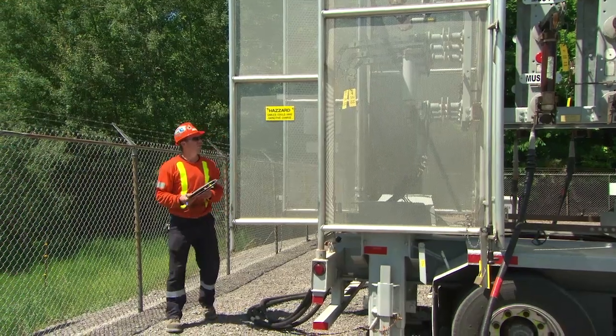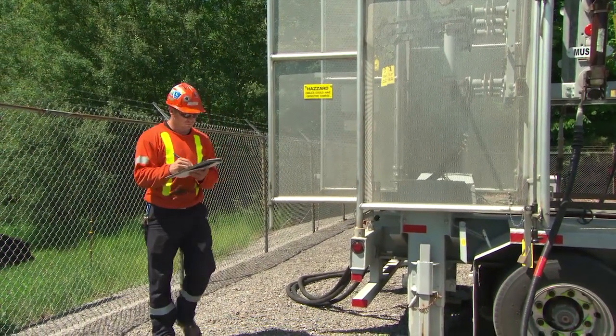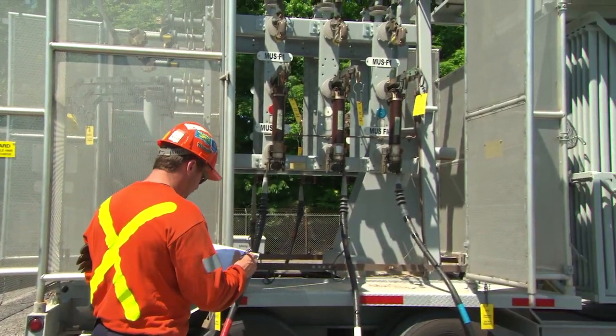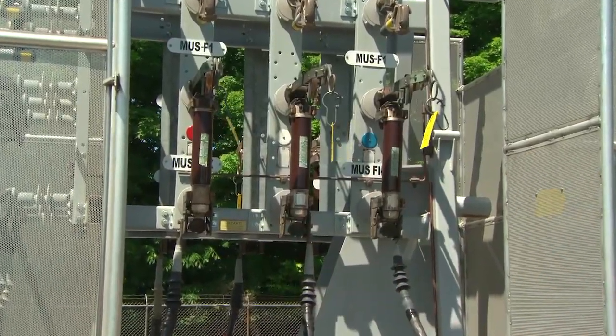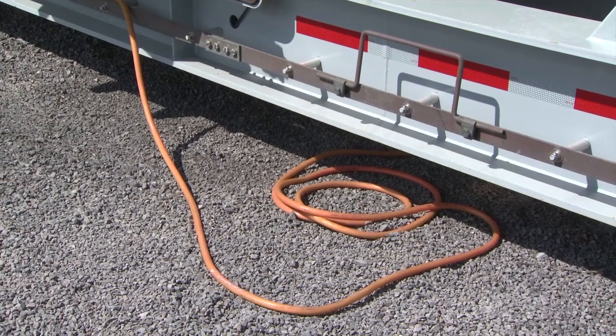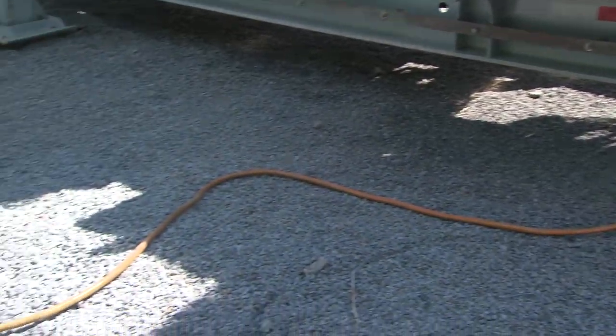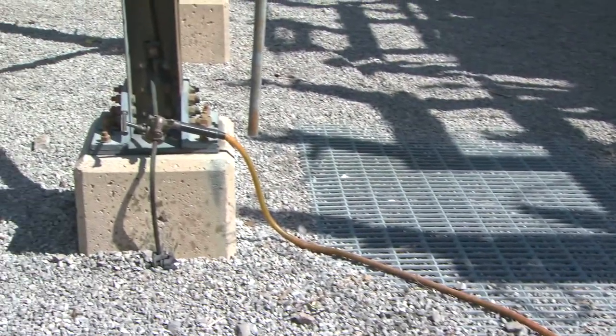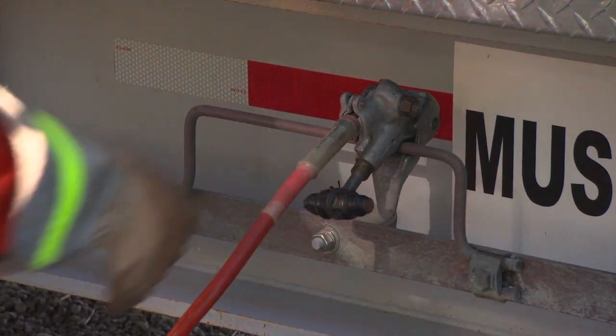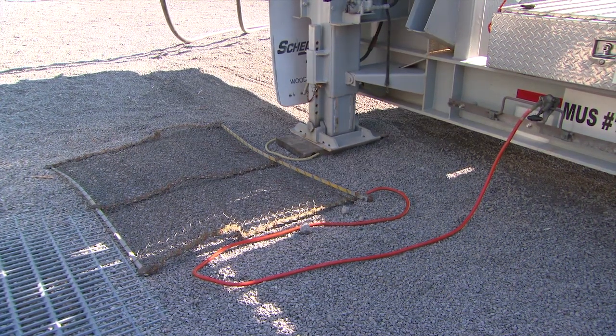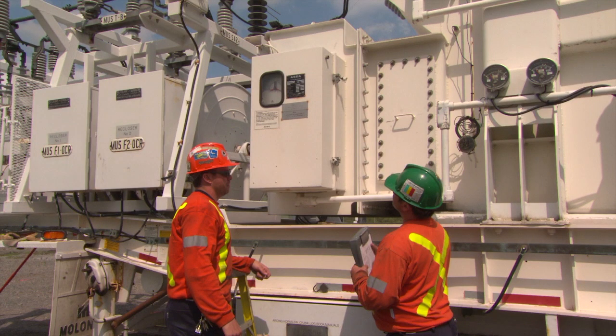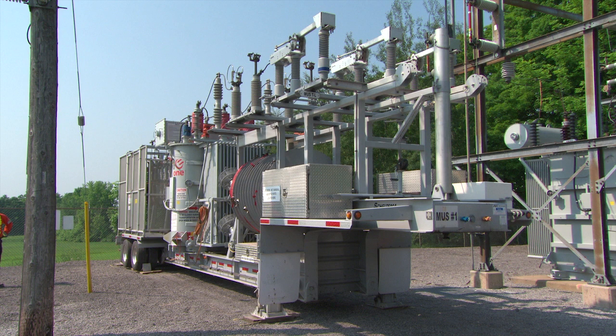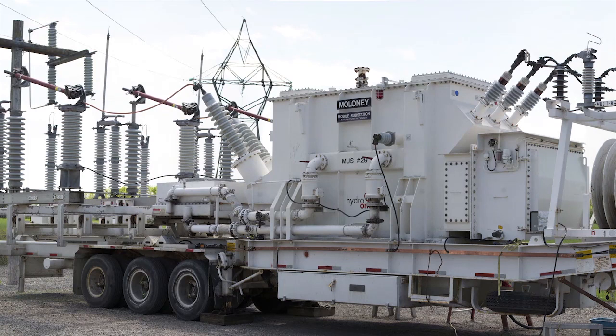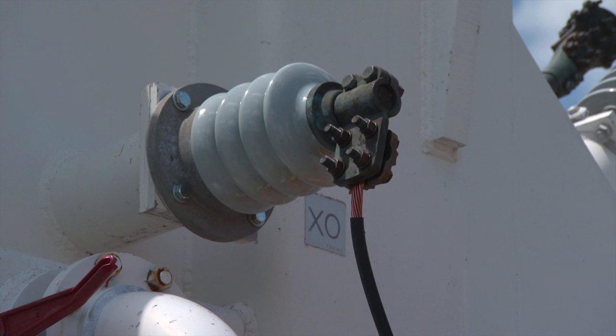Once the MUS is prepared for switching, it is best practice to perform a final walk-around to confirm that every necessary task has been completed properly. Check that the MUS grounds are still connected securely to the station ground. The high-voltage and low-voltage portable ground mats are in position and connected to ground. The MUS ULTC voltage sensing relay settings are matched to the station sensing relay settings. Clearances are maintained. Tools and equipment are clear. The wire braid is removed from the transformer and bus work. The XO bushing has been reconnected.